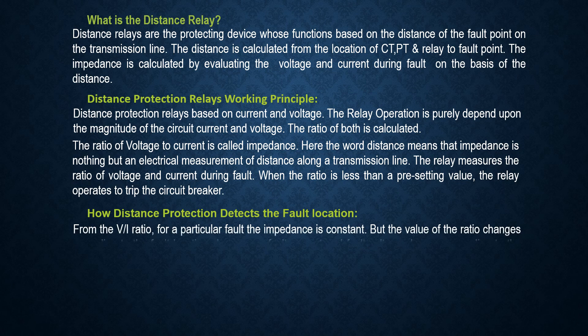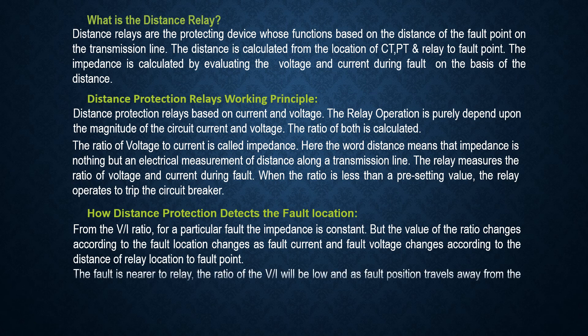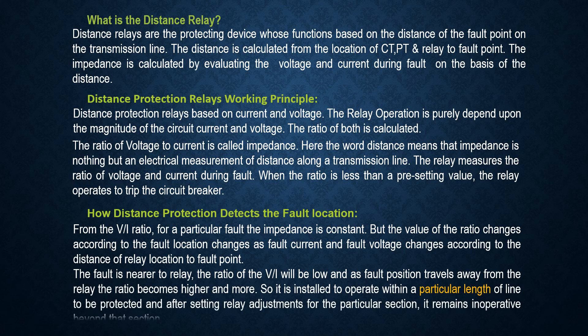From the V and I ratio, for a particular fault the impedance is constant, but the value of the ratio changes according to the fault location, as fault current and fault voltage change according to the distance from the relay location to the fault point. If the fault is nearer to the relay, the ratio of V and I will be low, and as the fault position moves away from the relay, the ratio becomes higher.